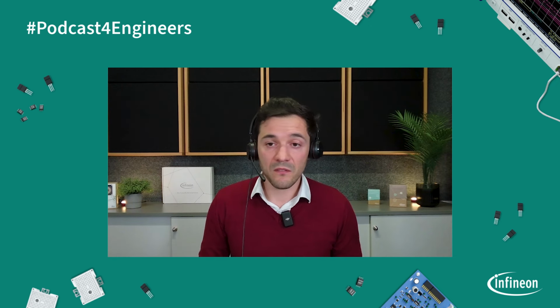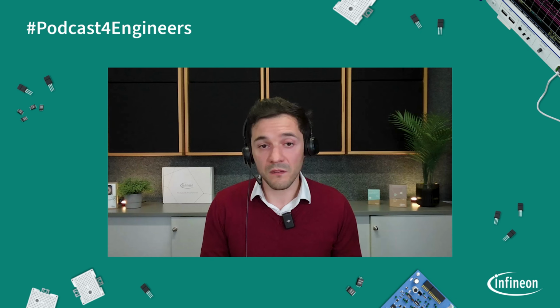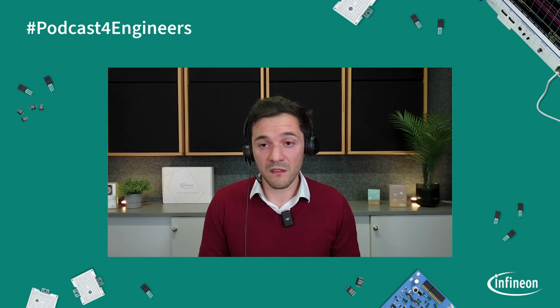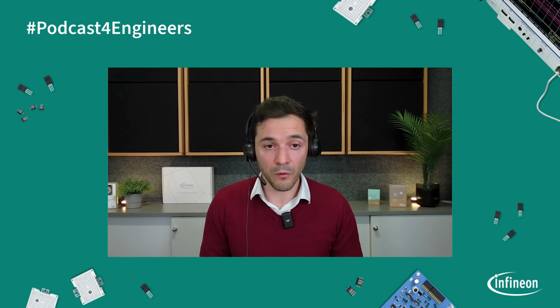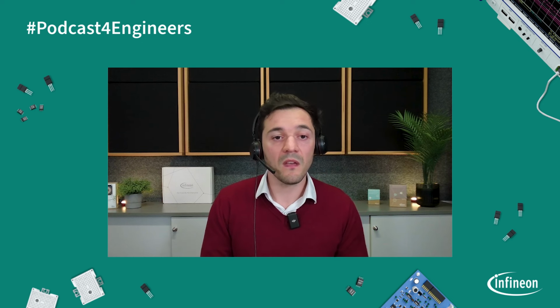Indeed, there are also ways and strengths to go further down, for example, 5:1, 6:1, and 8:1. 5:1 is something that has been considered in this system. It's not really popular nowadays, but we are actually working on that as well, because we can really perform at a very high efficiency, for example, with the HSC type of topology. And what is also interesting is that the maximum voltage faced by the VRM is 12 volt. 60, which is normally the maximum voltage in the OCP, 60 divided by 5 is actually 12 volt. So it's also very important for the reliability of the entire system.